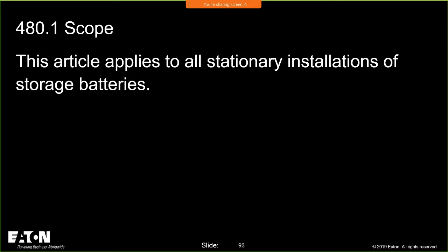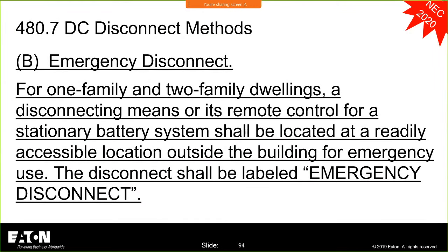So the article, they went back to 480, which deals with stationary installations of storage batteries. And they said that you have to have a disconnect for 1 and 2 family dwellings. Disconnecting means or its remote control for a stationary battery system shall be located at a readily accessible location outside of the building for emergency use, and it shall be labeled emergency disconnect. Now, I don't see any grouping requirements. It just says to be disconnected outside.